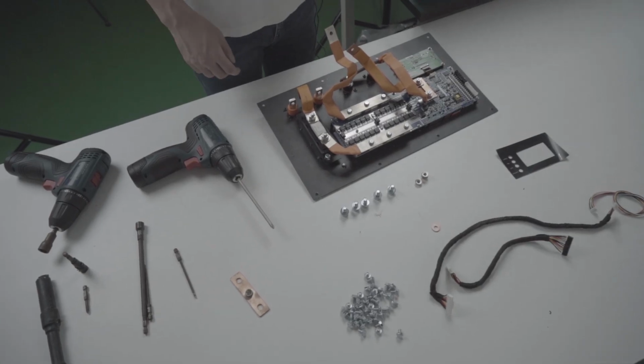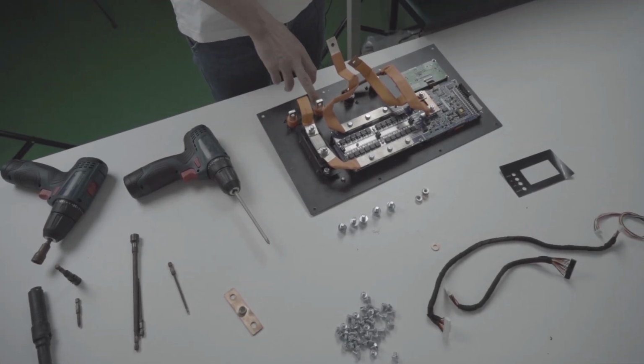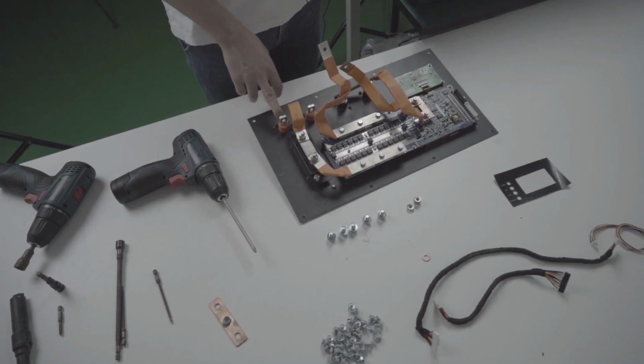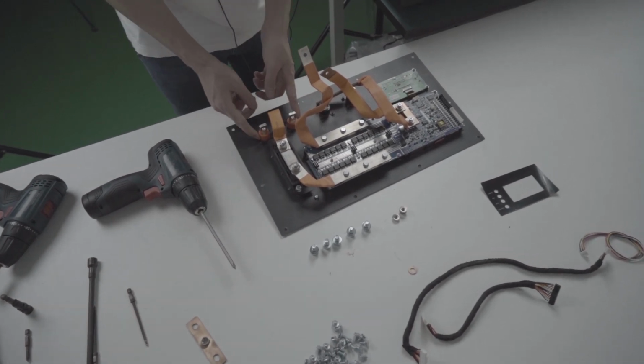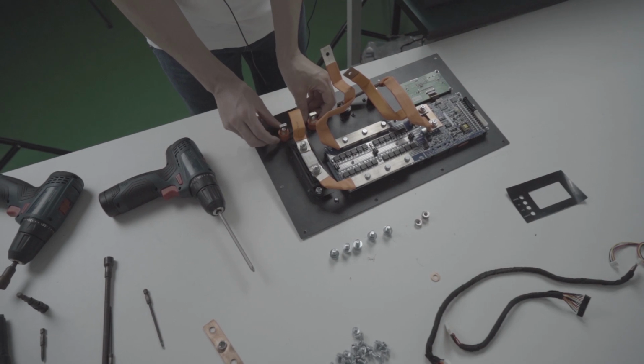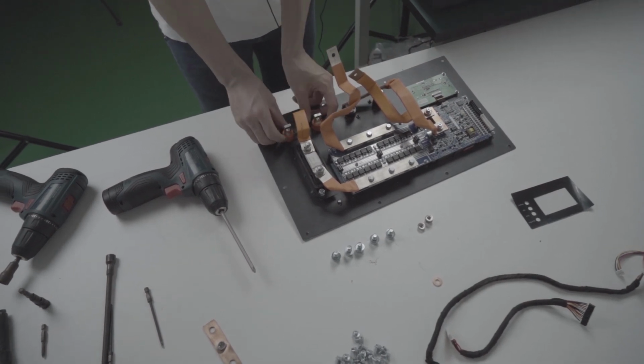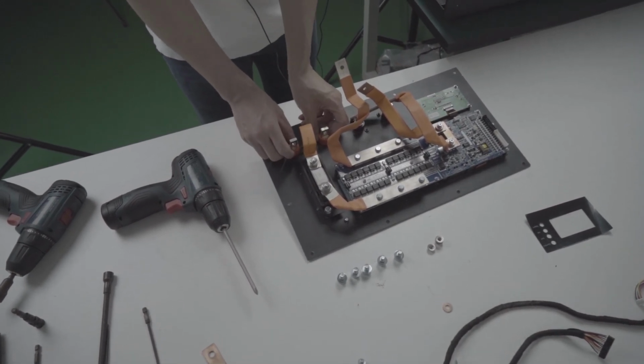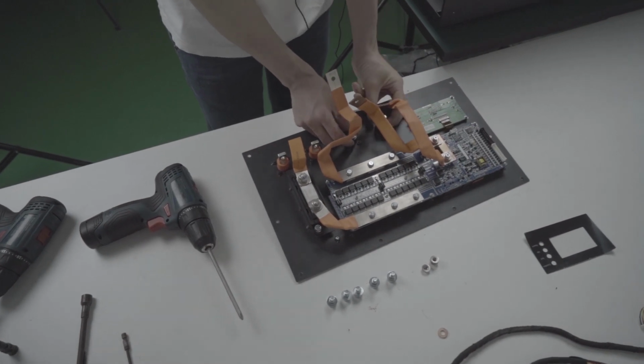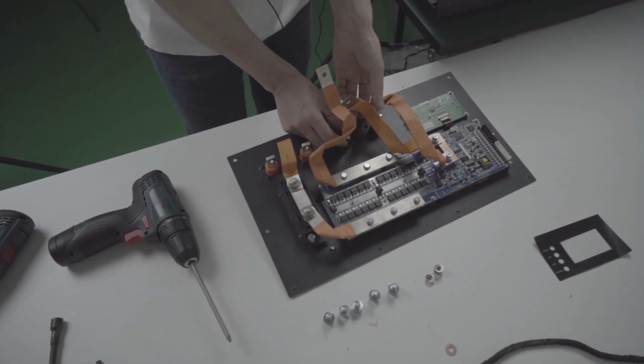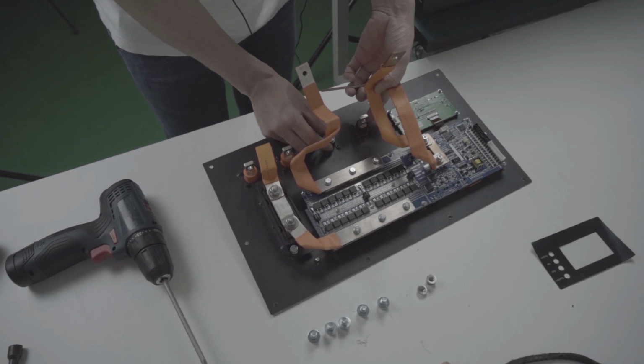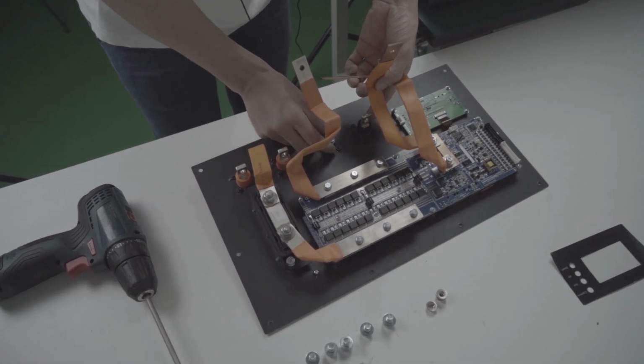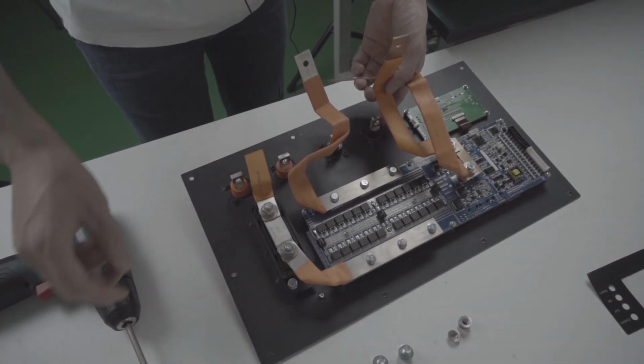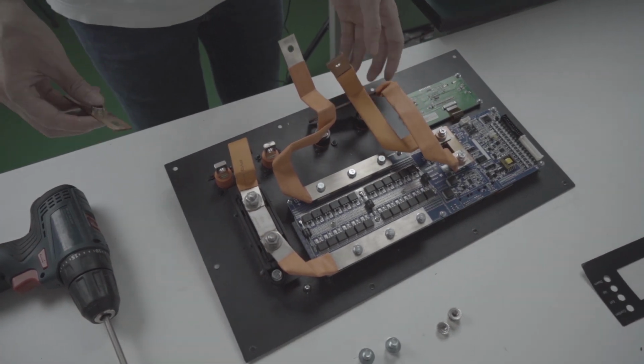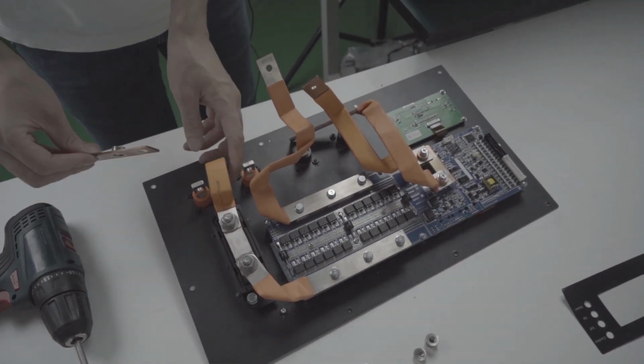Next we're going to parallel these 2 positive electrodes. As you can see, this is orange, they're marked in the color orange, so it means they are positive electrodes. There are 2 other poles, these 2 electrode poles marked black, and they're negative electrodes. Now we're going to parallel them with the copper bus bar.